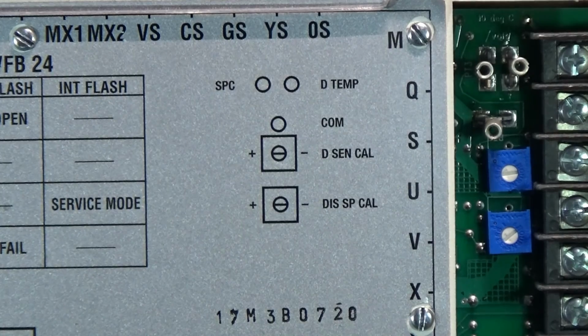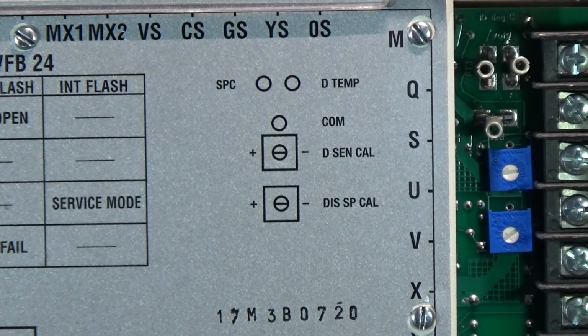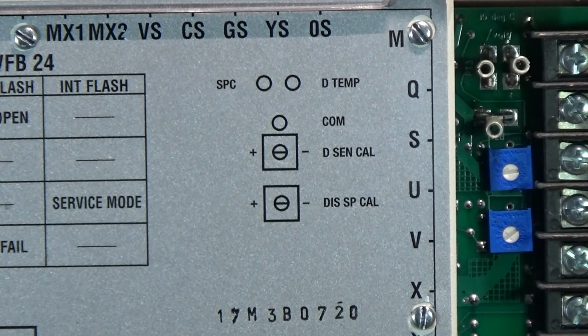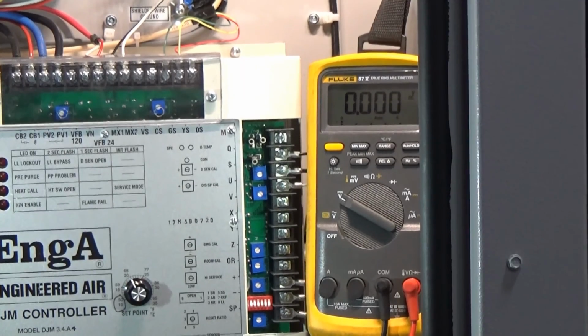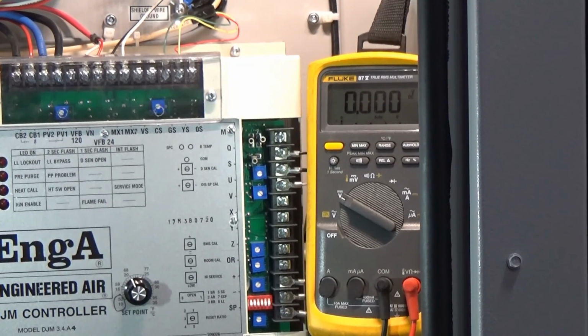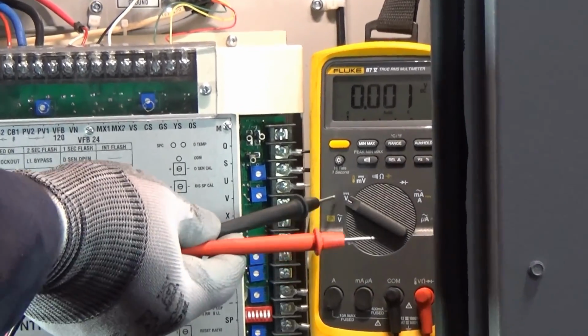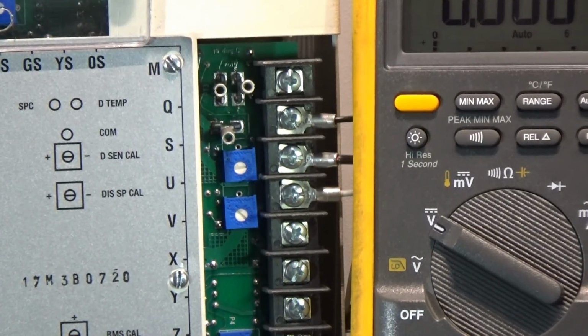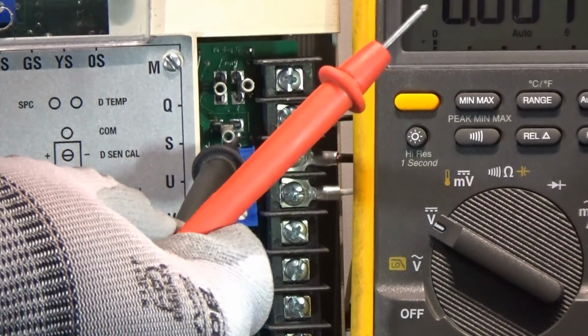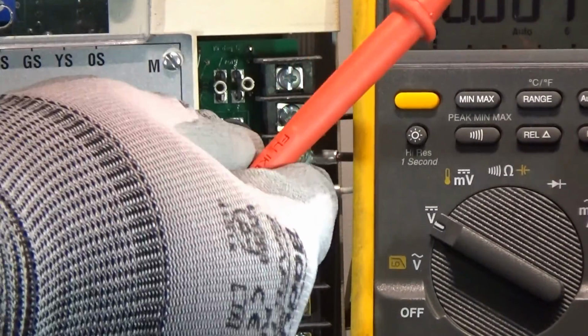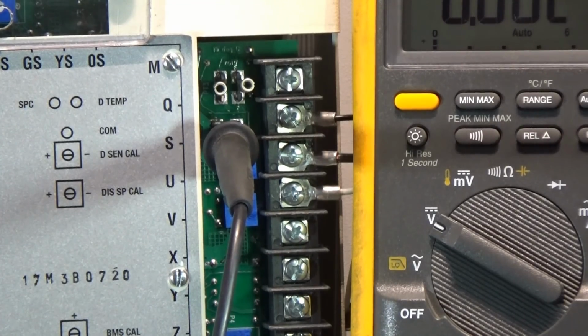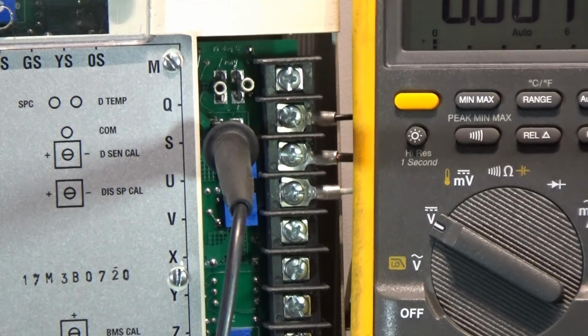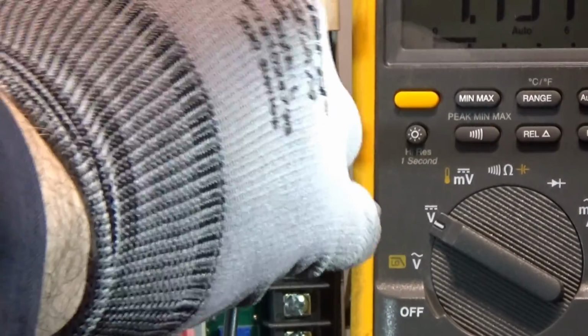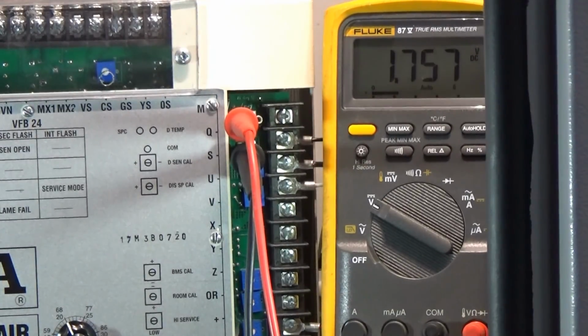Once you've determined the type of setpoint that is controlling your unit, locate the 3 test pins by terminals M, Q, and S. These 3 test pins will give you a readout of your final calculated setpoint and discharge sensor temperatures. With the controller powered, set your multimeter to volts DC. The single test pin at the bottom is your common. Insert your neutral lead there. The test pin on the left, labeled SPC, is your set point calculation. Insert your positive lead there. You will now have a readout on your multimeter.